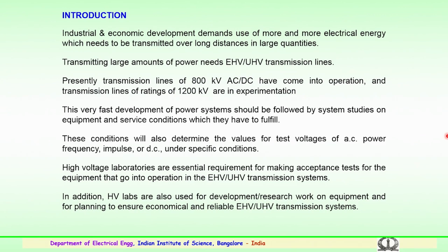So, this very fast development of power systems should be followed by system studies on the equipment and the service conditions which they have to fulfill in the field. These conditions will also determine the values of the required test voltages. It could be AC power frequency voltage of 50 hertz, or a lightning impulse which is 1.2 by 50 microseconds, or a switching impulse of 250 by 2500 microseconds, or an oscillatory type of impulse which is seen in the field, or it could be DC voltages under specific conditions.